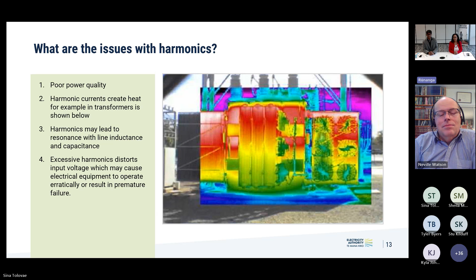So when we go to the store, if we get buy one, get one free, we might be happy. But if we get 50 hertz current, and we have hundreds of harmonics superimposed on top of that, it's not a good thing for the power system. It leads to poor power quality. It causes heat. And in many cases, if the distribution utility assumes that a transformer might last for 20 years, it might fail or get damaged within 10 years, and one of the reasons might be harmonics. It also damages loads on the consumer side and in data centers. So we don't want to have these harmonics. We can only manage them; we cannot avoid them.